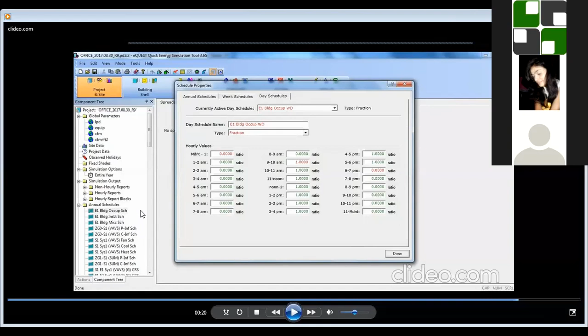And this is the schedule which I have discussed earlier. I've just shown you an occupancy schedule, from midnight through the next 24 hours, with all the schedules given. Whatever the operating time of our office, mall, retail, hostel building or hospital, whatever the building, a schedule will be assigned based on the building type. Nowadays, the schedules have been defined in the standards as well. ASHRAE and ECBC have their own schedules. If we are going for any ECBC models, then the schedule given by the standard has to be directly implemented here. I'm showing this only for occupancy, but it is also available for lighting, miscellaneous, then AC systems and fan operation. Everything is given separately.